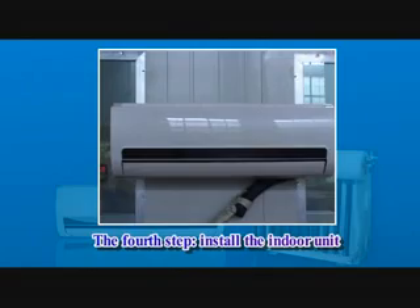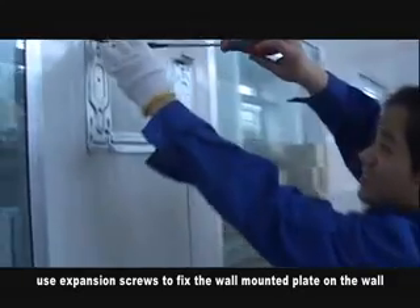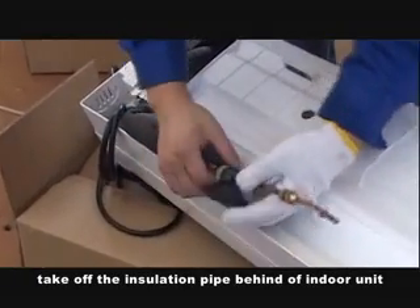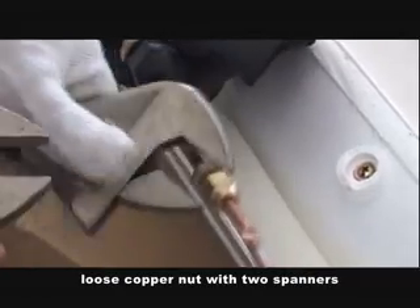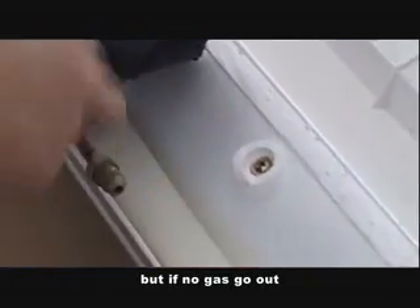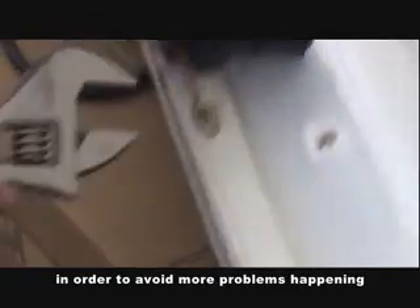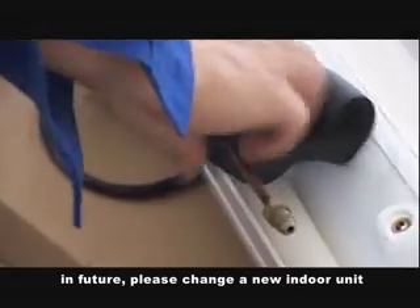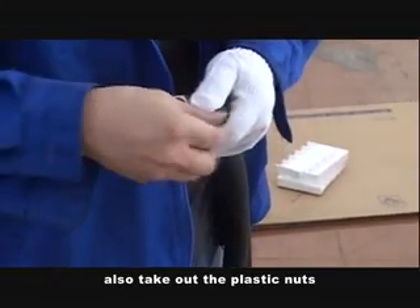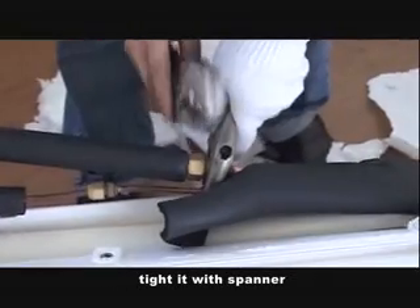Fourth step: install the indoor unit. Take out the indoor unit and remove the wall-mounted plate. Use expansion screws to fix the wall-mounted plate on the wall. Take off the insulation pipe from the back of the indoor unit. Loosen the copper nut with two spanners. If there is gas coming out, the indoor unit is not leaking. But if no gas comes out, it may mean the evaporator of the indoor unit has a leak — in that case, please replace with a new indoor unit. Take the connecting pipe of indoor and outdoor unit out, along with the plastic nuts. Fix the two connecting pipes of the indoor unit after straightening them, and tie with a binder.